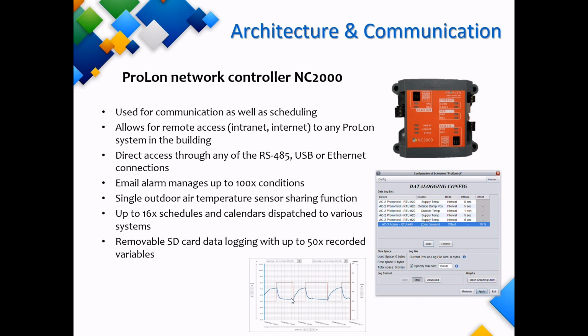Last but not least is the trending feature. We can configure this controller to log any variable on the system, and we choose how often it logs that variable, whether it be every 30 seconds, every minute, every 5 or 10 minutes, whatever works best for the contractor. All this information is stored on an SD card, which can be inserted in the NC2000, so we are not using any internal memory of the controller for this log. Since we are using an external SD card to store all the information, it can record and hold the data from several weeks, months, or even years worth of operation.